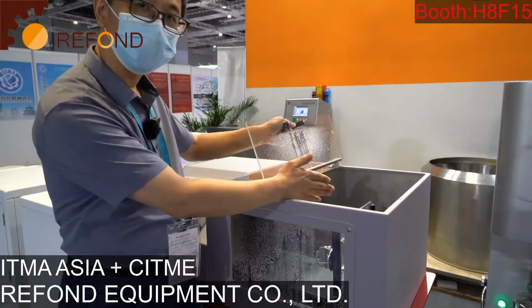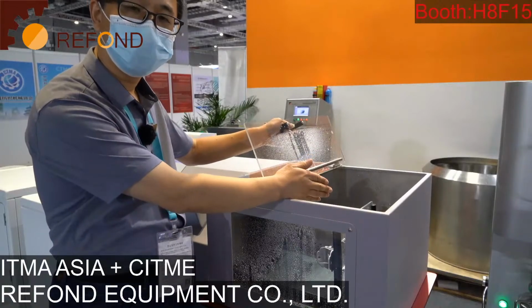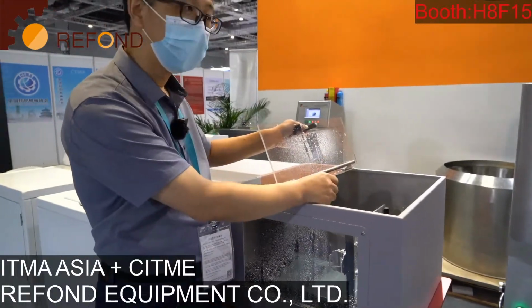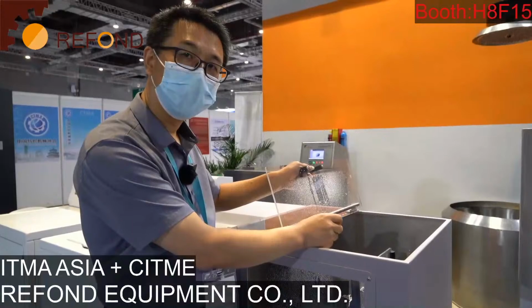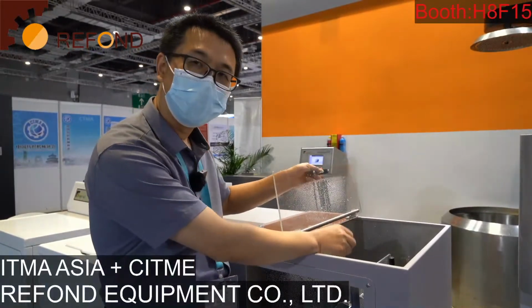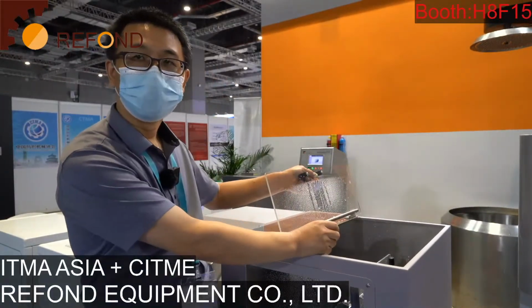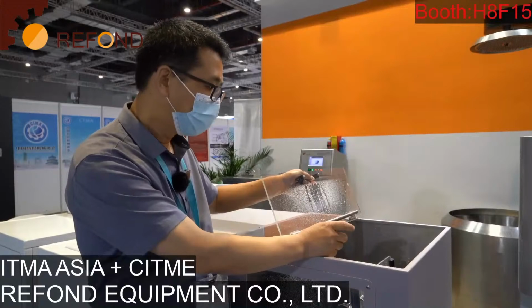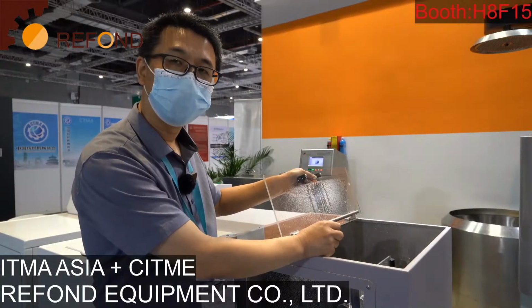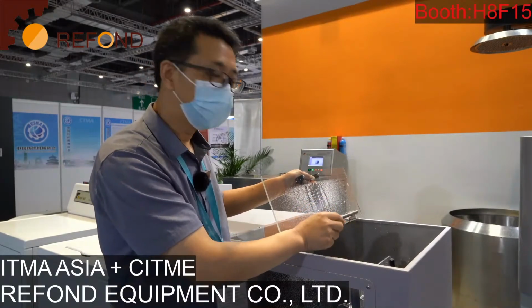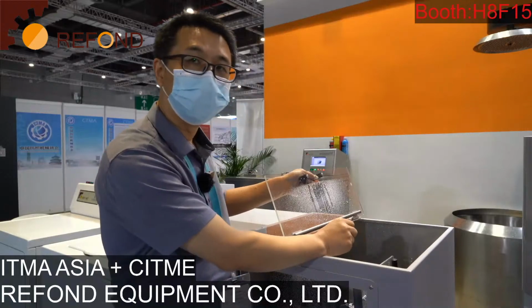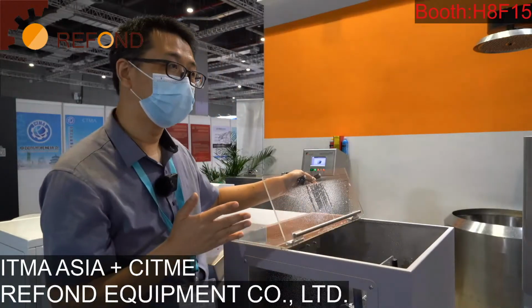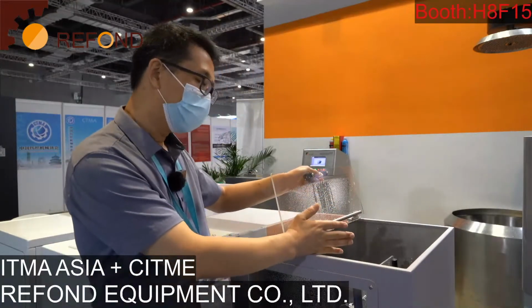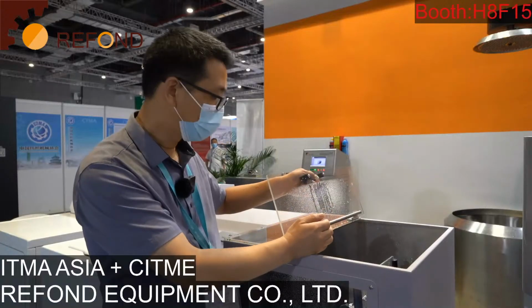After doing the test for 5 or 10 minutes, take the specimen out and remove the blotting paper to check the weight. How much water has been absorbed by the blotting paper. This is the function of the rain tester.